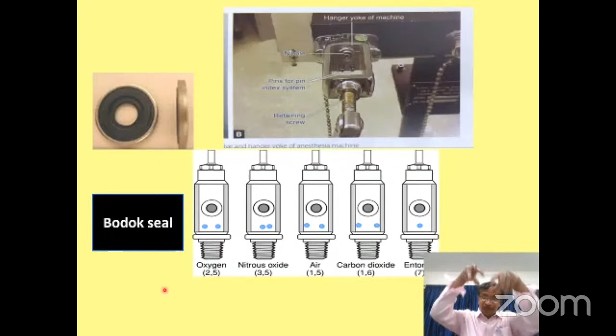So we cannot put nitrous oxide because it is 3,5. The holes and pins will not match. So that is why you cannot. This is one of the safety systems, the pin index safety system. This pin index safety system is also available in some of the flow meters. Flow meters are coming down now. There will be 2 pin indexes. So here in this pin index, Entonox is 7, air is 1,5. This is about the pin index.